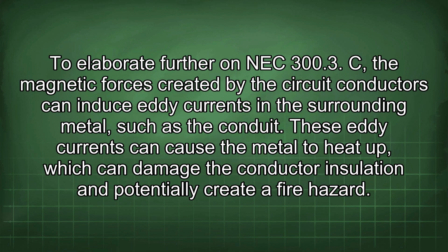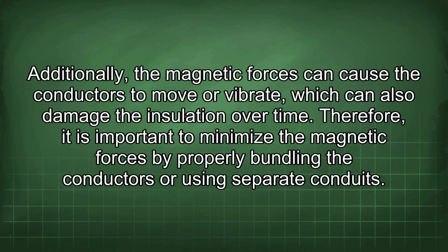To elaborate further on NEC 300.3(C), the magnetic forces created by the circuit conductors can induce eddy currents in the surrounding metal, such as the conduit. These eddy currents can cause the metal to heat up, which can damage the conductor insulation and potentially create a fire hazard. Additionally, the magnetic forces can cause the conductors to move or vibrate, which can also damage the insulation over time. Therefore, it is important to minimize the magnetic forces by properly bundling the conductors or using separate conduits.